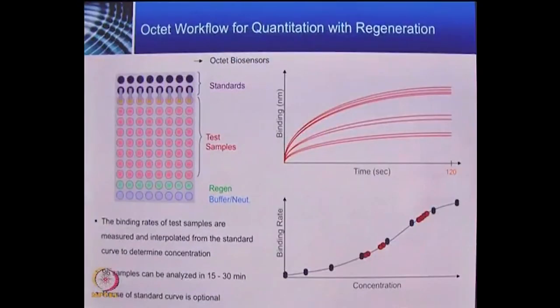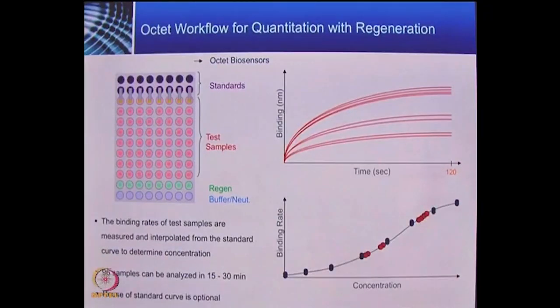One advantage of using BLI technology for concentration analysis is the ability to analyze multiple samples simultaneously. It takes only about 15 to 30 minutes to finish analyzing 96 samples. Depending on the assay, biosensors can be regenerated, meaning you only need 8 or 16 biosensors to analyze a full 96-well or 384-well plate. This dramatically facilitates the application of BLI technology in both the pharmaceutical industry and academic research.